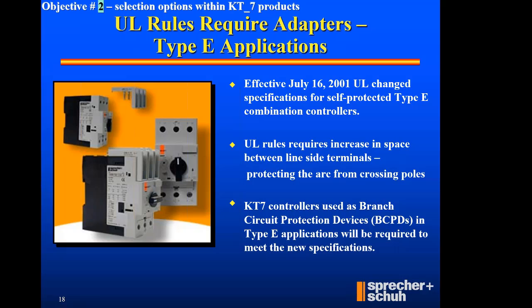So that's kind of unique. You've got to be aware that if I'm going to use Type E rules, I need some sort of space in between the arcs. If I've got a single device, I can use a TE adapter. If I've got multiple devices, more than likely I'm utilizing bus bar with a feeder block feeding that bus bar, and that bus bar feeder block does comply with a 2-inch creepage space, and a TE is not provided. We just have to make sure you've got that extra space off the top side of that line side device.